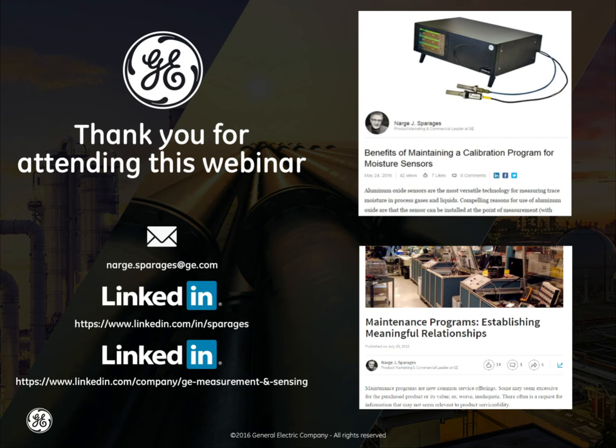Next question was, is the initial calibration at the manufacturer performed with a sensor filter on the probe? There is a 100 micron sintered shield that protects the sensor when we ship it, in the cases where we're shipping it for gas applications. And there is a stainless steel sheath for liquid applications. That is installed during the calibration. So it's there to protect the sensor as it's being handled in terms of our calibration. And then for you in the field, it's there to protect you from causing mechanical failure by bumping the sensor against the sample system wall, etc. So yes, the initial calibration is performed with the sensor filter in place on the sensor.